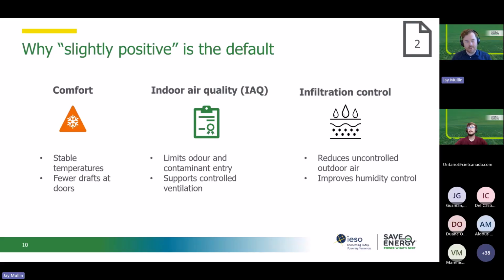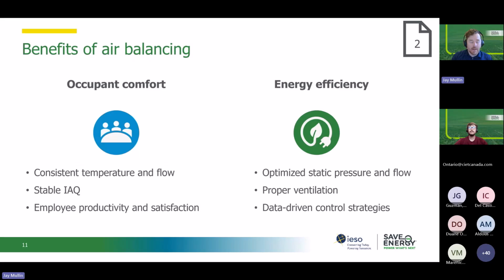So it's generally recommended for industrial facilities to keep a slightly positive pressure. A typical target I've seen is around 0.01 to 0.03 inches of water column differential. So 2.5 to 7.5 pascals. So not big. But we often see facilities with a pretty significant negative pressure, usually because there's a lot of exhaust for industrial processes happening, and the makeup air isn't always properly balanced. So you may unintentionally have high negative pressure, or even in some cases, if it's the other way around, unintentional high positive pressure. Balancing that out has a number of benefits for occupant comfort.